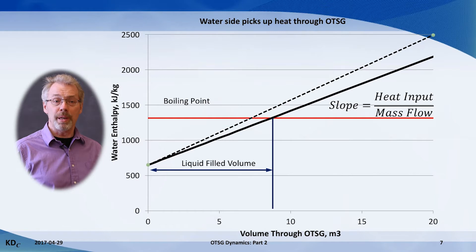If the firing rate increases, then there is more heat added through the OTSG volume, and the OTSG produces higher enthalpy and higher quality steam. This makes sense. This is represented on our graph as the line having a steeper slope.